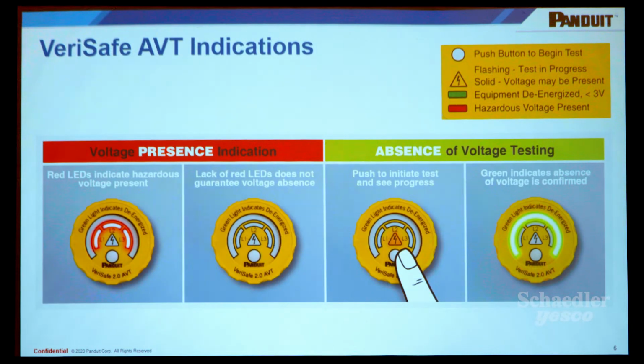So this is what it looks like at the door. It's a very simple red, yellow, green scenario. When power is to the panel, you get a voltage indication, which is shown right there. You show your 3 phases, and if a phase were to drop out, it would indicate that as well. So it does voltage indication. Once you disconnect power to the panel, the indicator module goes blank, right? At that point, you hit the test button, and it'll flash yellow while it's under test.